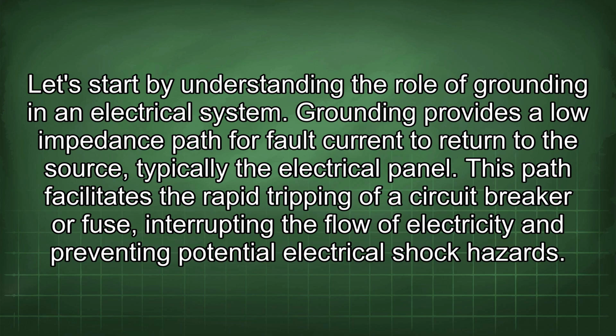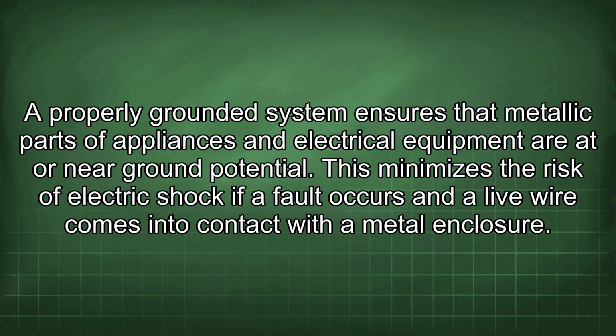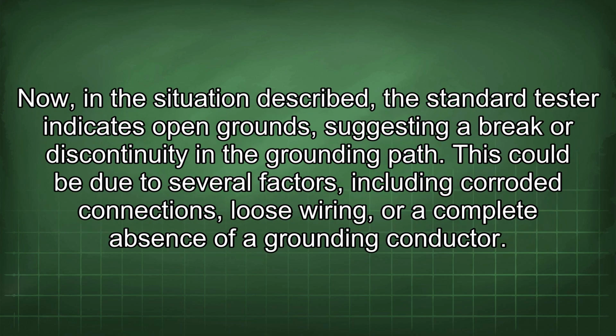electrical shock hazards. A properly grounded system ensures that metallic parts of appliances and electrical equipment are at or near ground potential. This minimizes the risk of electric shock if a fault occurs and a live wire comes into contact with a metal enclosure. Now, in the situation described, the standard tester indicates open grounds, suggesting a break or discontinuity in the grounding path.